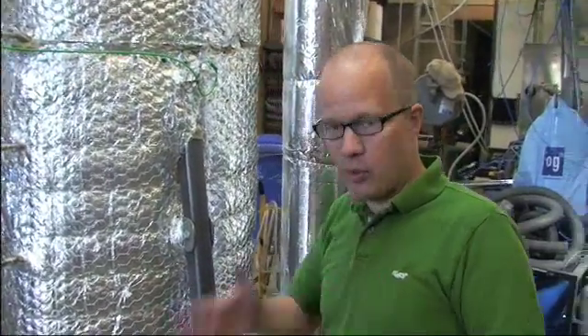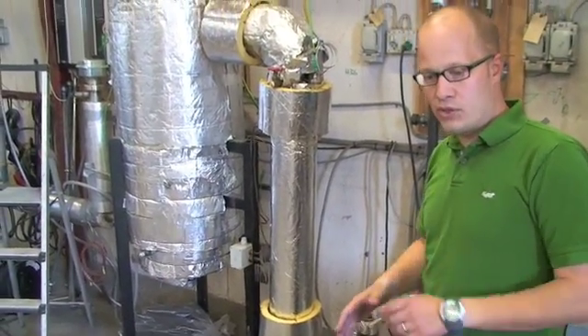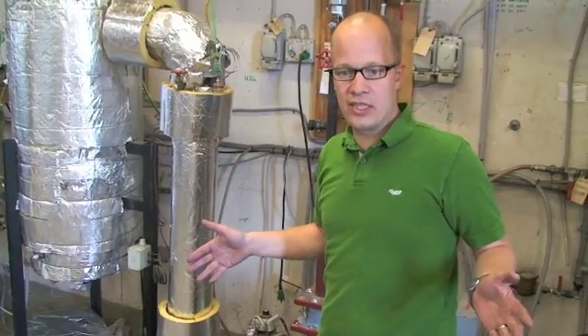So there are not the obstacles that exist in a conventional heat exchanger. What we have here is actually a small particle filter — a fabric filter. These are bags about this size where the gas goes through and up inside the bag. Afterwards we have a gas which still contains all the tars but is free of particles. Just by doing this we widen the scope of utilization of the gas significantly.